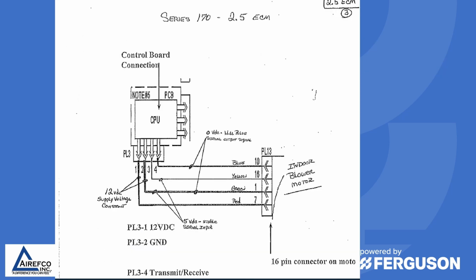As we stated previously, you will have high voltage to the ECM motor at all times, but you will not have communication to the motor unless it's calling for the motor to run. So as we said, you will need the manufacturer's troubleshooting guide for each particular model that you're working on to see what type of voltage you should read from the control board to the motor to command it to run and to stop. A note here, make sure that when you're checking these voltages, you check the voltage coming out of the board to make sure the board is outputting the correct voltage. And if you're not getting that voltage at the motor, then you probably have a problem with the plug or the wiring harness.